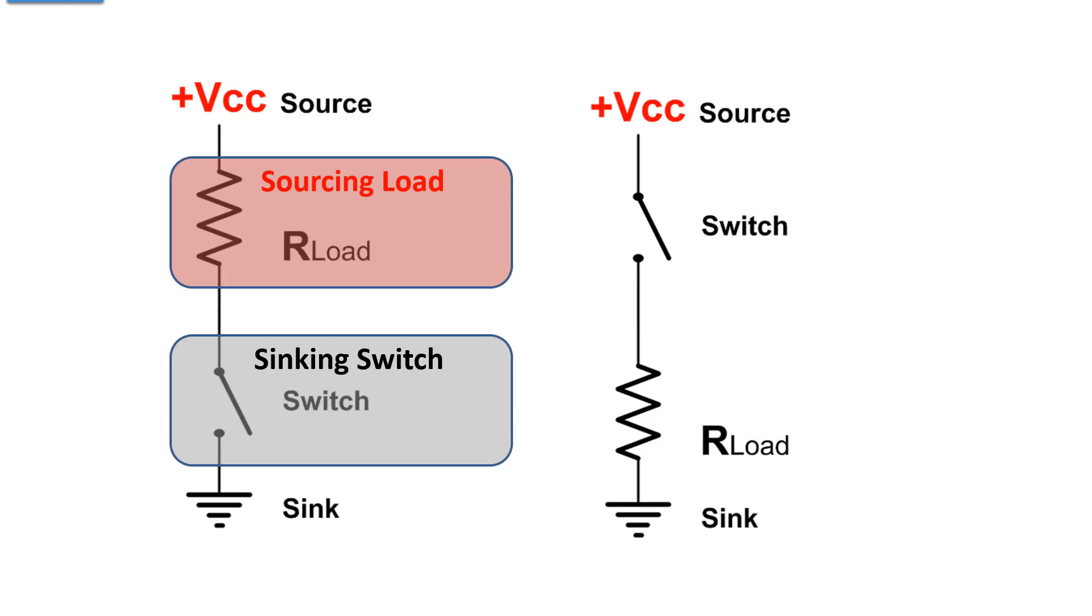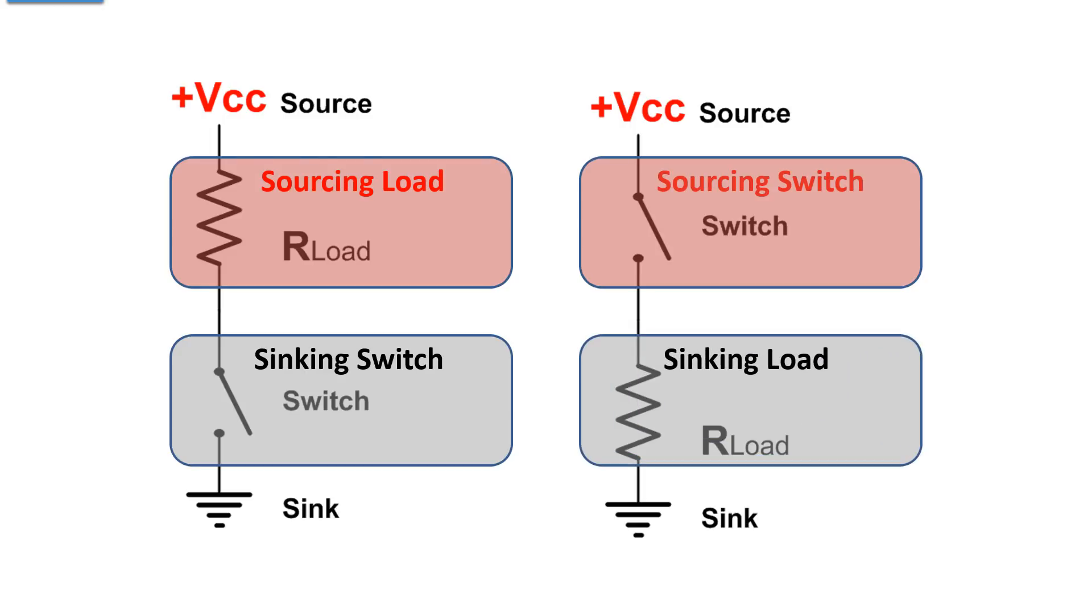If you swap the control switch and the load positions in this circuit, the switch is now sourcing and the load is sinking. It's that simple. Whichever of the two, the control or the load, whichever of the two is closest to the source is the source. Whichever is closest to ground or the sink is the sink.